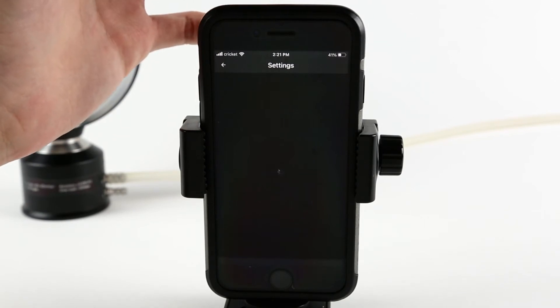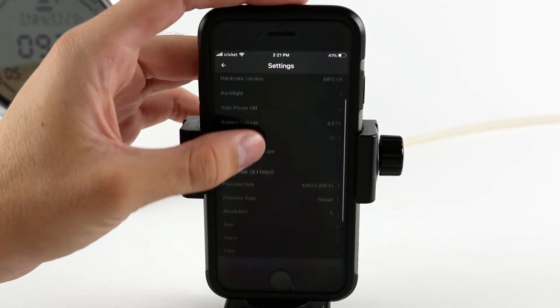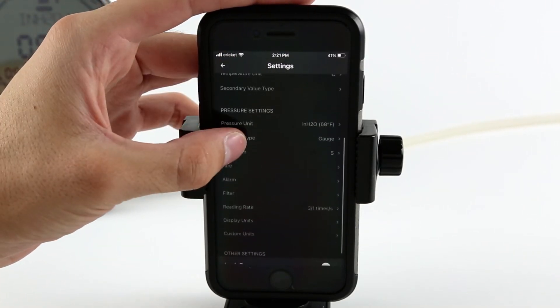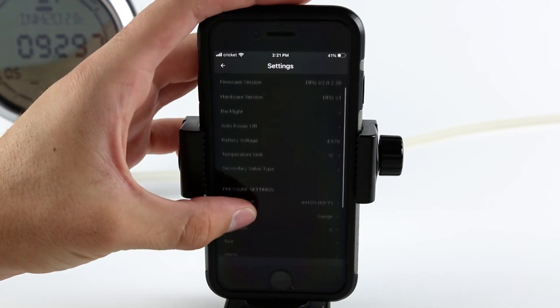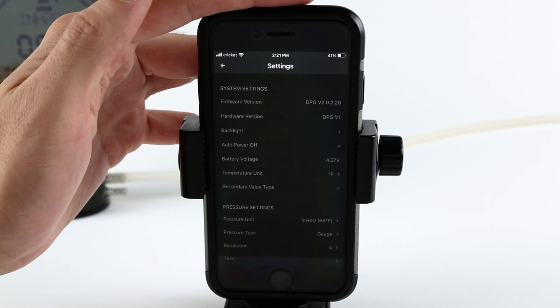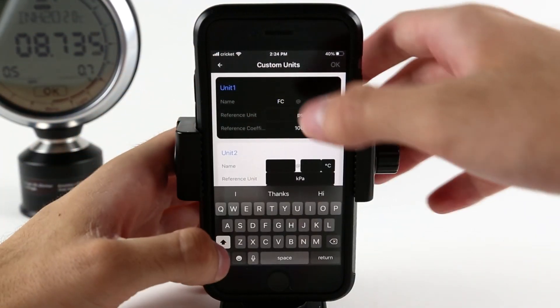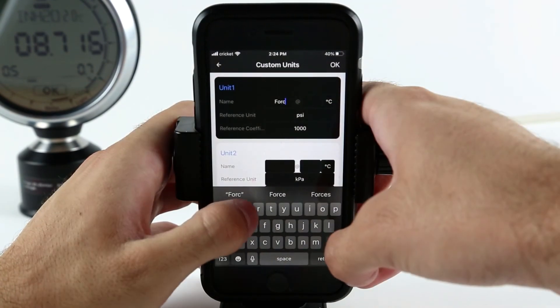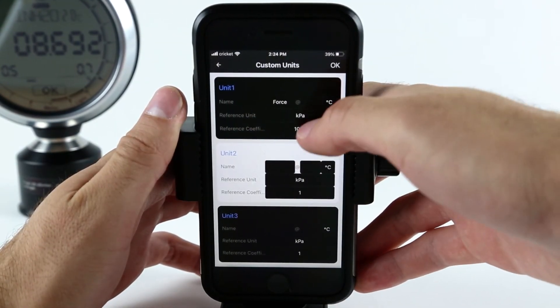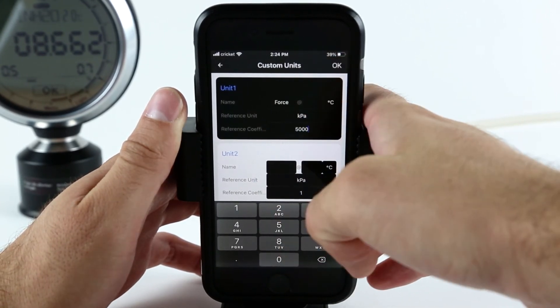Nearly all gauge information and settings of the ADT-685 can be easily accessed and changed through Additel Link. Adjust power settings or change the temperature or pressure units. Absolute or gauge measurement can be selected along with alarms, tare, or filtering. Additel Link allows for up to three custom units to be named and configured. Each custom unit allows for a factor to be applied to the reference pressure unit. When configured, these custom units become available on the ADT-685 unit selection.